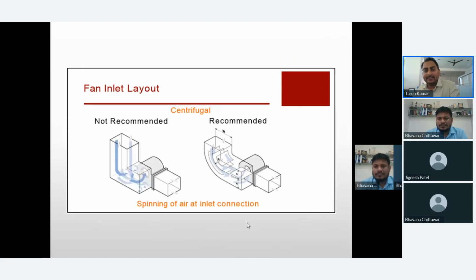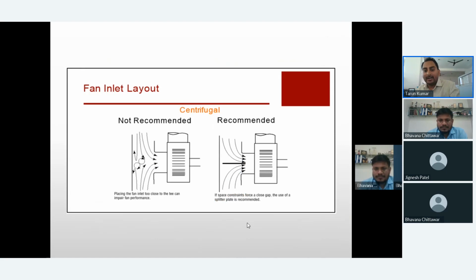If you have a constraint and can't put in straight duct, you should always use some splitter arrangement so that your air is guided properly and you get what the fan is designed for. Suppose there is some CFM and static pressure; these CFM and static losses will occur at bends, so we should try to avoid bends. Again, if branches are there, we always have to put in some splitter arrangement so that air is guided properly and your system is more effective.